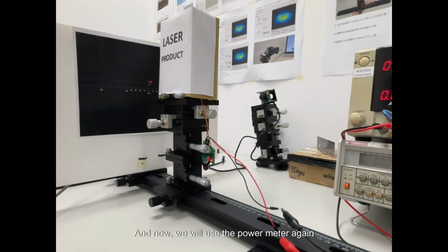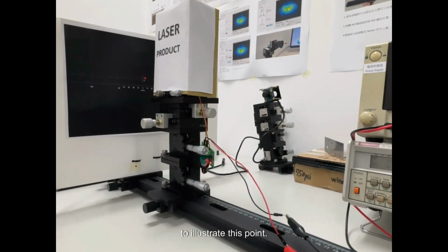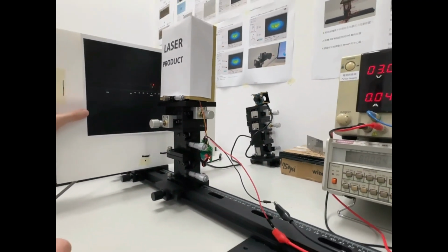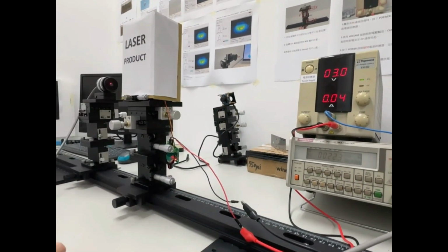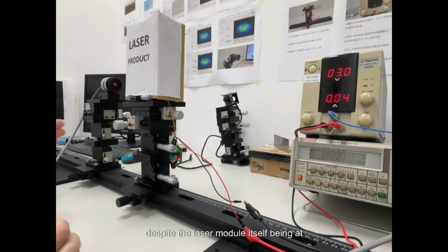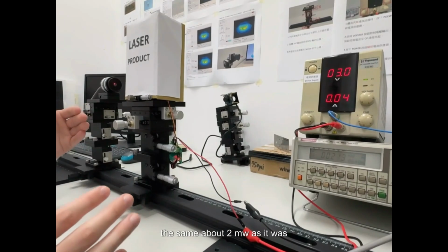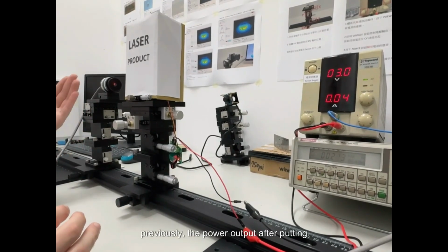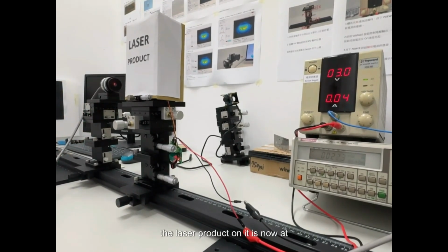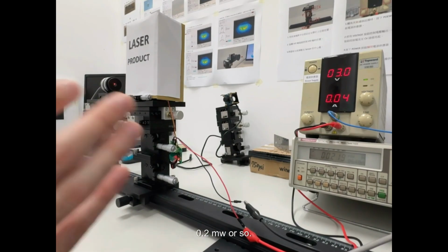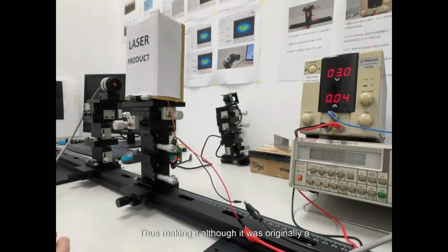And now we will use the power meter again to illustrate this point. So now, despite the laser module itself being at about the same 2 milliwatts as it was previously, the power output after putting the laser product on it is now at 0.2 milliwatts or so. Thus, although it was originally a class 3 laser, it is now a class 1 laser product.